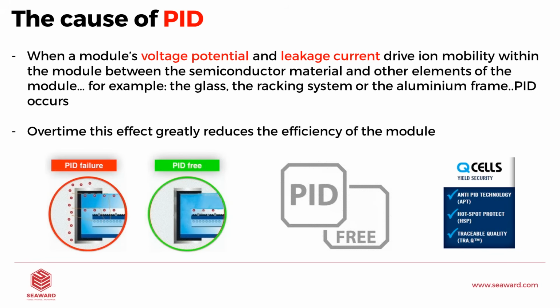So what we're finding these days is that a lot of 1500 volt panels, modules, are coming with this stamp of PID free. For instance, Q cells have this, Trina have this. So when you're looking to pick solar panels for 1500 volt installations, be aware of PID and the effect it can have on your system. So this probably won't affect, in fact, it definitely won't affect any new system you're commissioning. But if you're going back to a legacy system and you need to test it and you see issues with the voltage, most likely that is going to be PID. And that's why we're seeing more and more solar panels coming through that are glass on glass, using rubber clamps. And this really insulates the photovoltaic cell so it's not affected by PID. Or less affected, I should say.